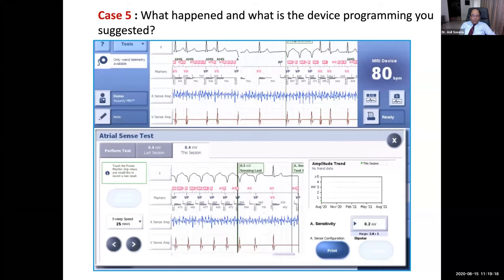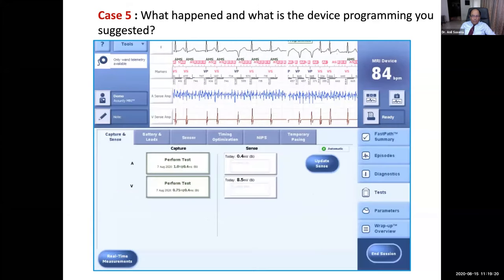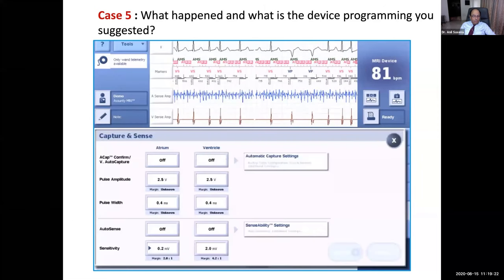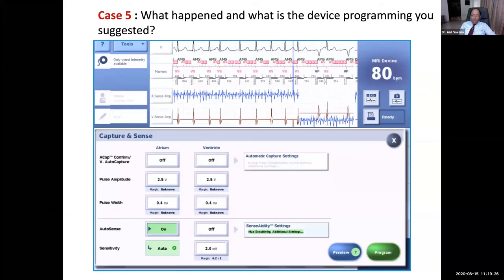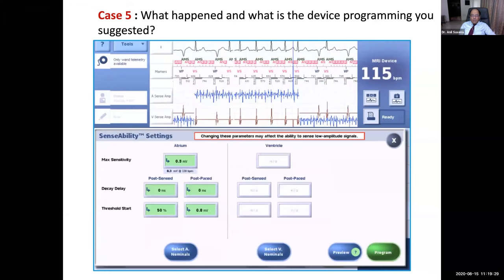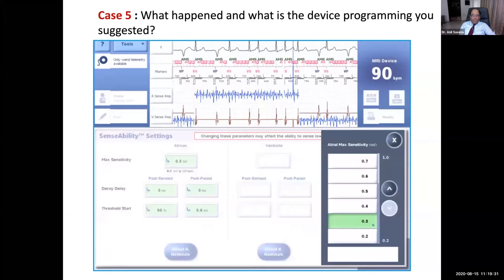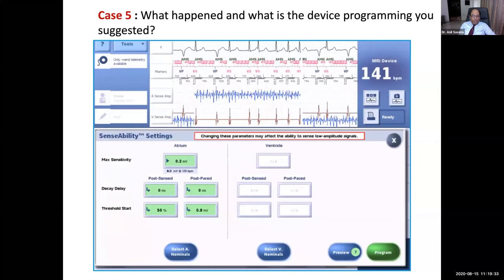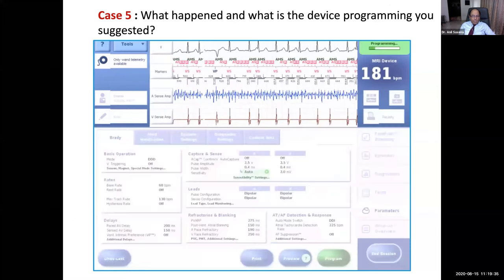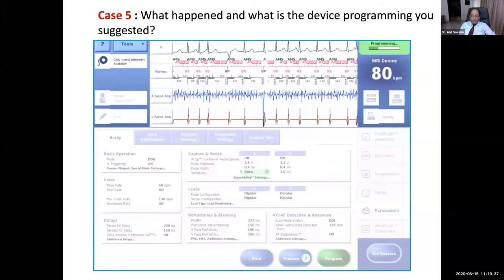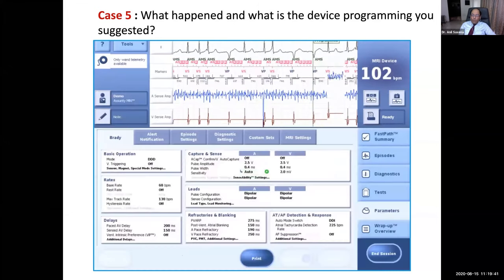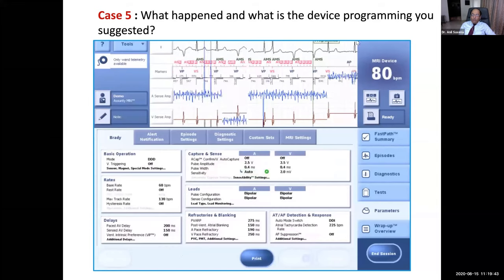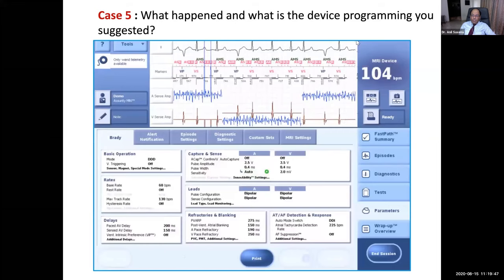Now there is another feature in some pacemakers, in Abbott they have it, SenseAbility, which is like a dynamic sensitivity as you see in implantable defibrillators. So the value we program is maximum sensitivity, and it does an auto adjustment of sensitivity during the cardiac cycle. So it prevents oversensing, and it doesn't fail to sense the atrial fibrillation because it keeps changing the sensitivity during the cardiac cycle.